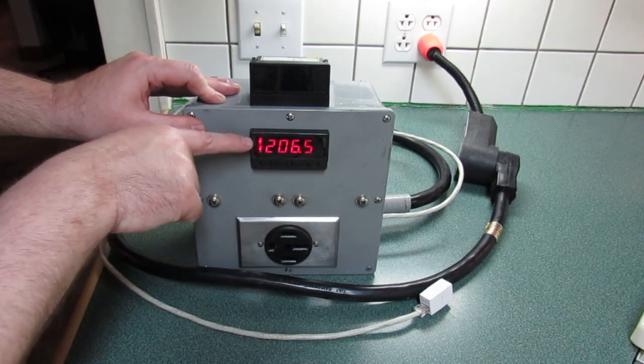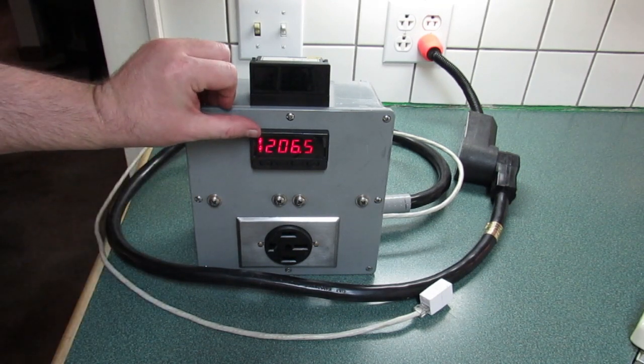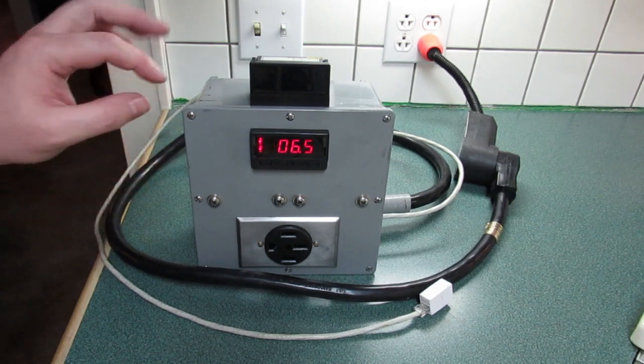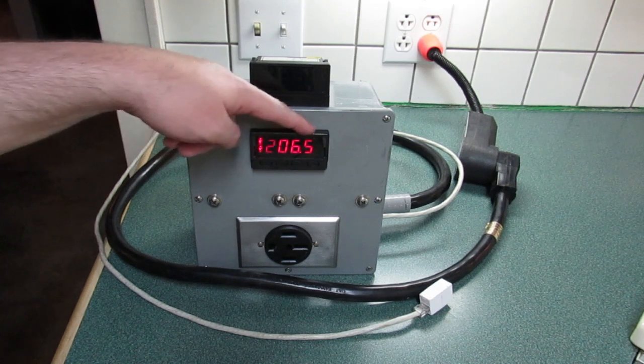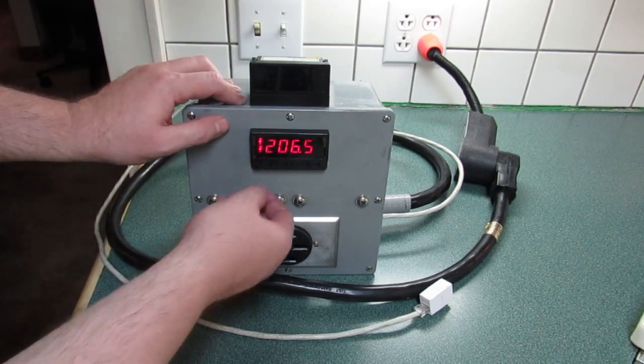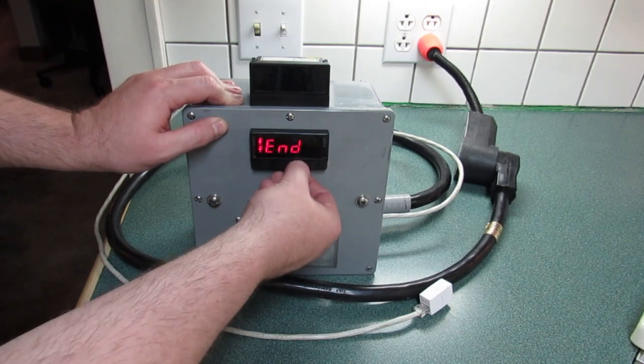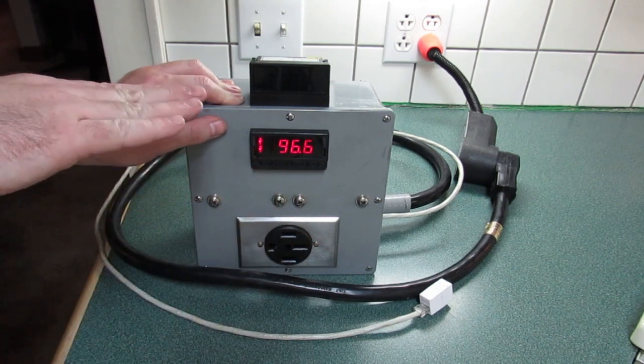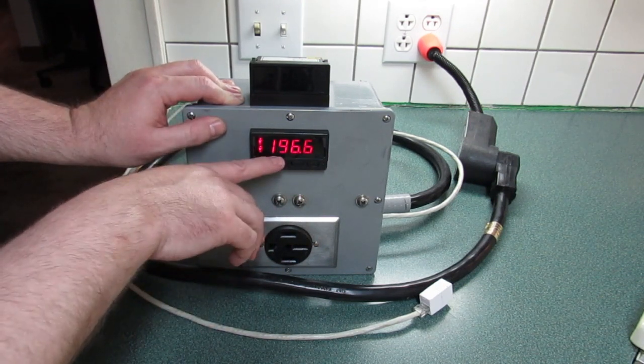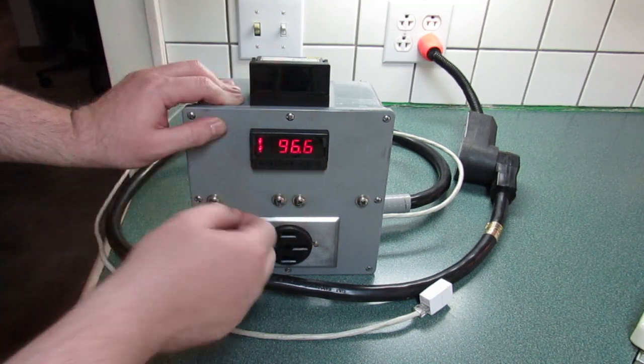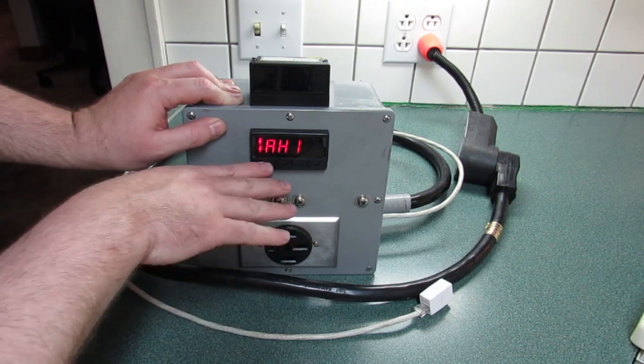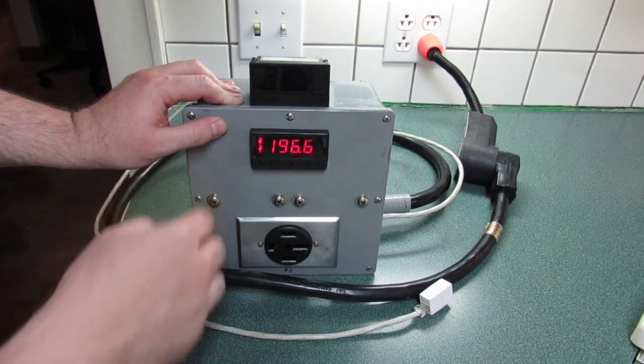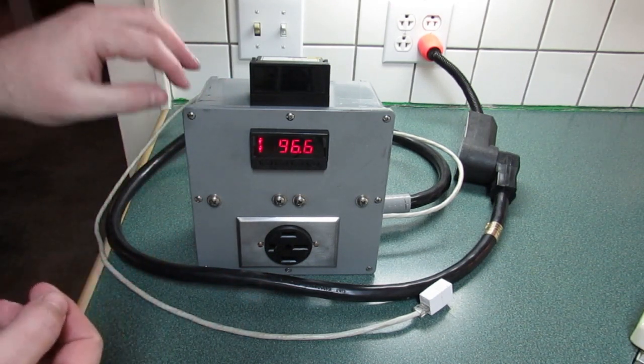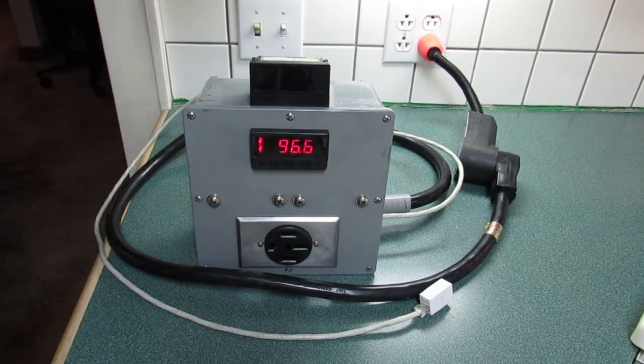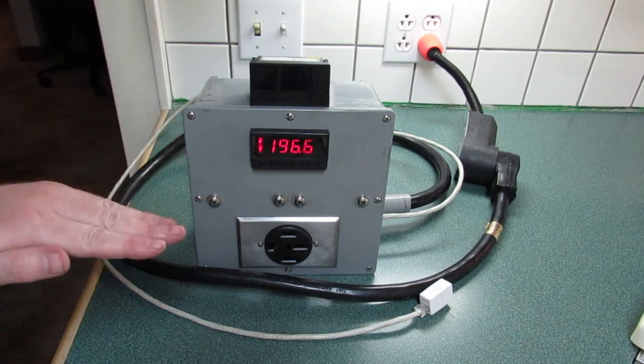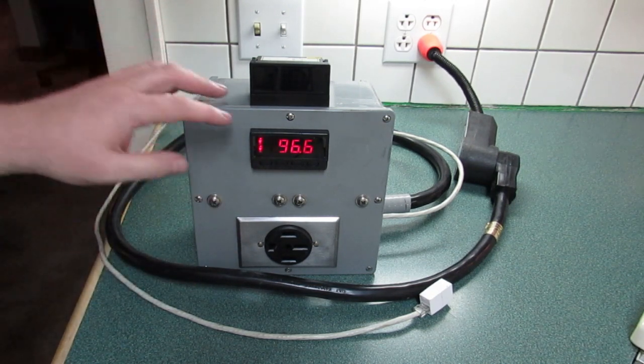So it will turn on this little relay right here, the top one, anytime the voltage is below 206.5. As soon as it hits 206.5, it's going to kick that relay off. And then it will stay off until the batteries hit 196.6. If they go below the low of, which is set to the high one, below that value, then this relay will turn back on and it will stay on until it hits that 206 again. So that's kind of your hysteresis of charging up to full, shuts off the charger, lets it settle down to 196.6, and then turns it on again, and so on and so forth.